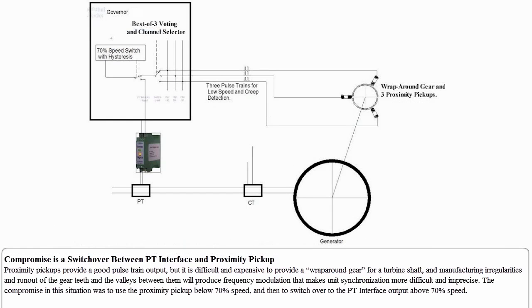Proximity pickups provide a good pulse train output, but it is difficult and expensive to provide a wraparound gear for a turbine shaft, and manufacturing irregularities and runout of the gear teeth and the valleys between them will produce frequency modulation that makes unit synchronization more difficult and imprecise. The compromise in this situation was to use the proximity pickup below 70% speed and then to switch over to the PT interface output above 70% speed.